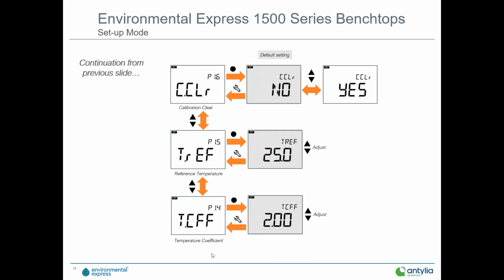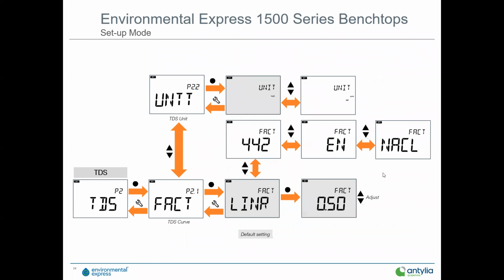A little bit more in the conductivity and TDS. Here's your temperature coefficient. Here's your reference temperature, which is adjustable, and then your data or calibration clearing capabilities. Again, enter with the enter button, exit using the settings button. Pretty straightforward. TDS, again, you can set up your curve. You can pick the curve, the linear curve, the 0.5 curve. From there you can jump up and do units, obviously, with this. With the TDS curve you pick, you have to go to linearity and then up to the 442 curve, or the DIN EN 7888 curve, or the sodium chloride curve.